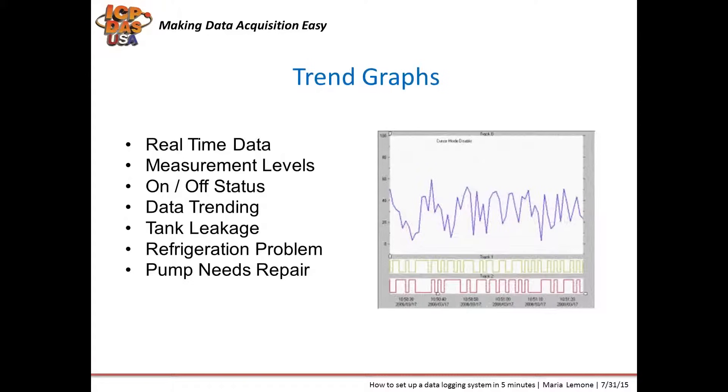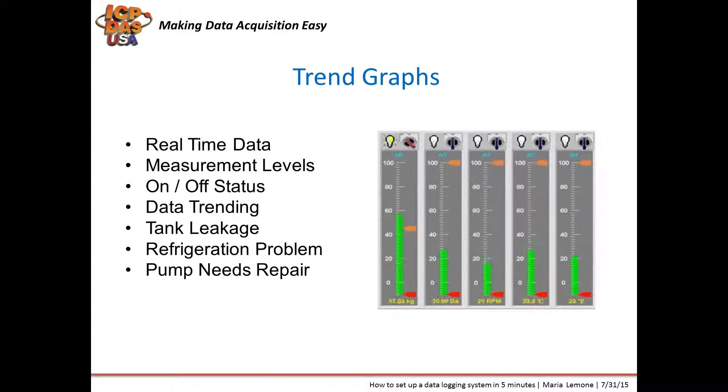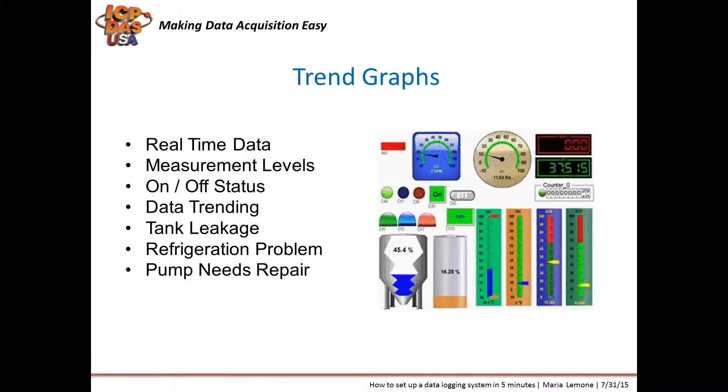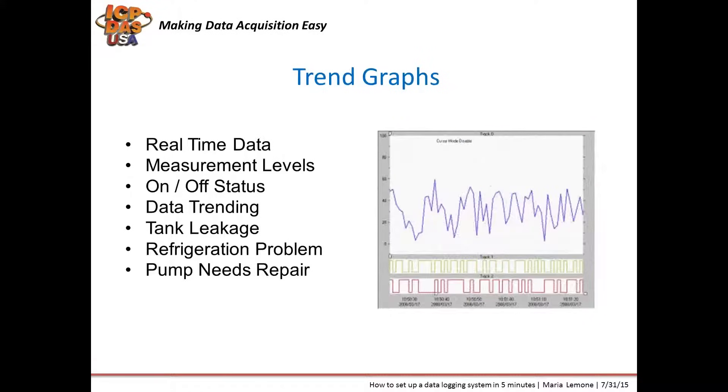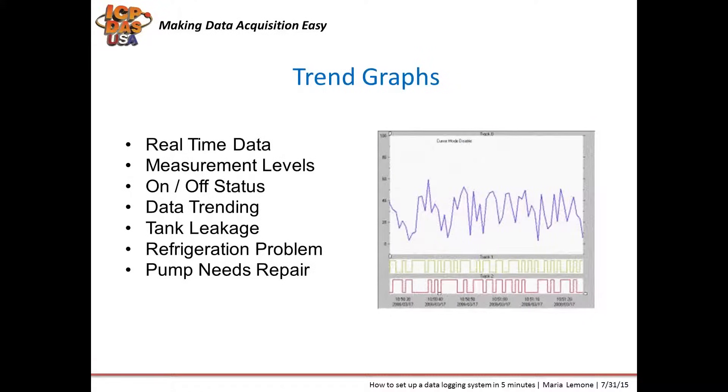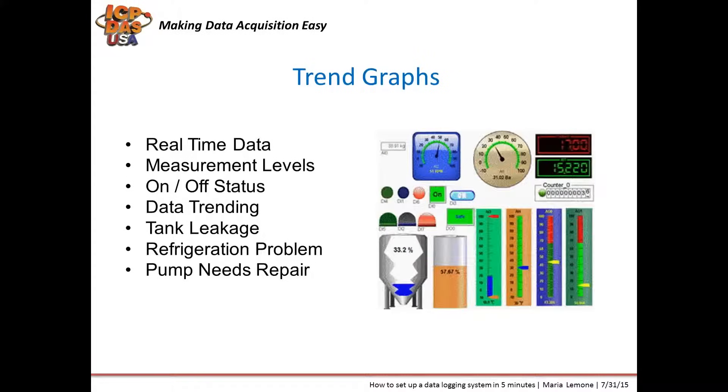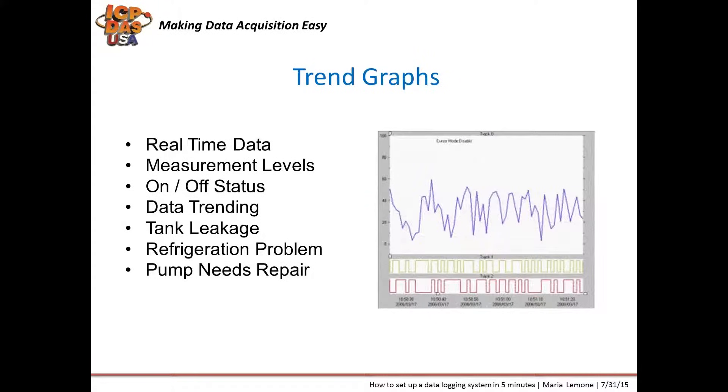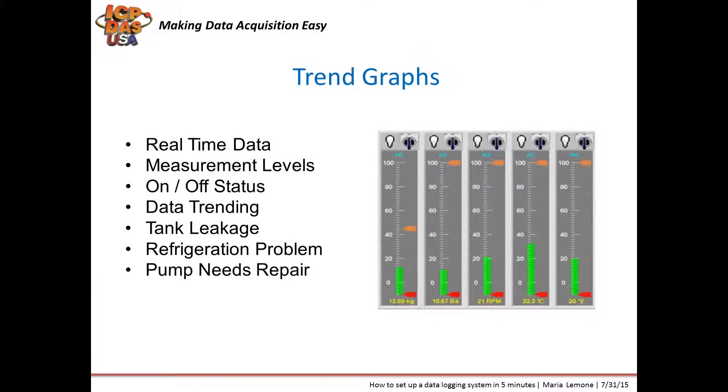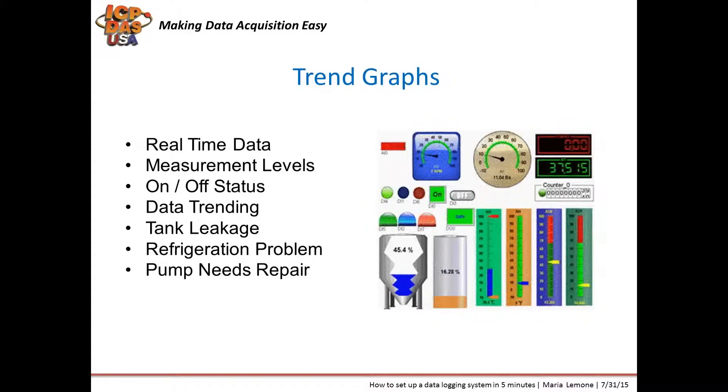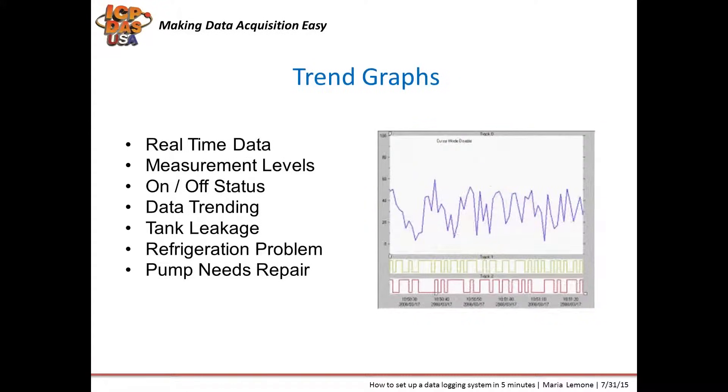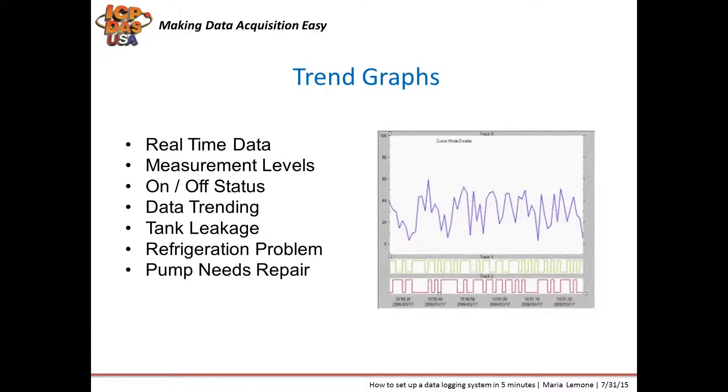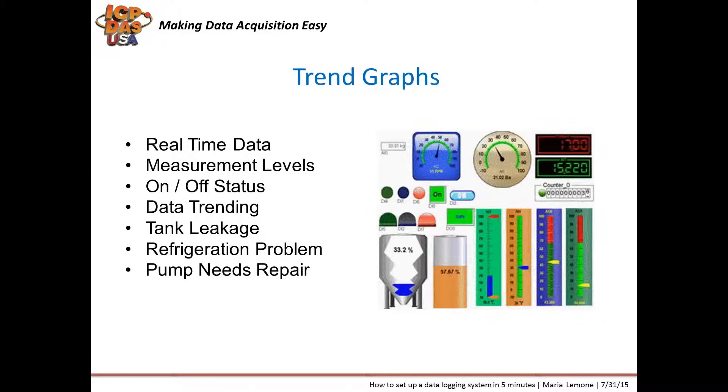Data log information can be shown on a graph, so you can visually see the data plotted on a chart over time. You can see the real-time data for the current status, which can show what the measurement levels were over a past hour, day, or year. You can also see the waveform, the on-off status of digital equipment. The trend graph can indicate a tank leakage, a problem with refrigeration, a pump that needs repair, all of which can save money if the problem is found sooner rather than later.